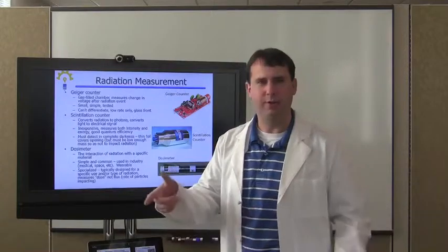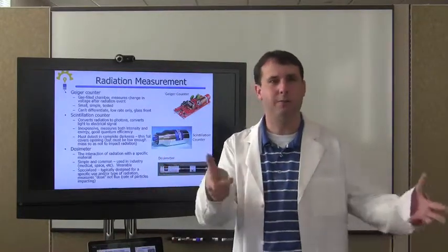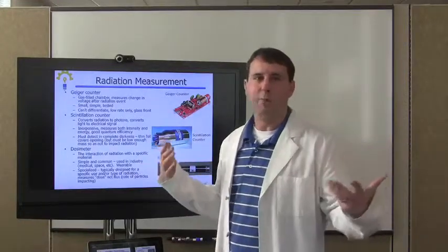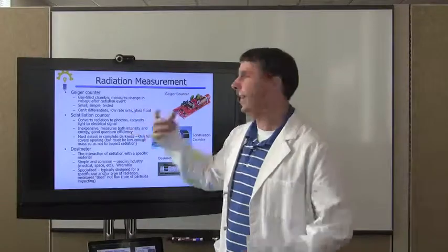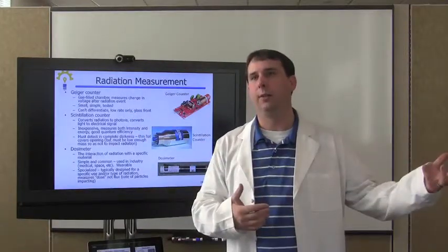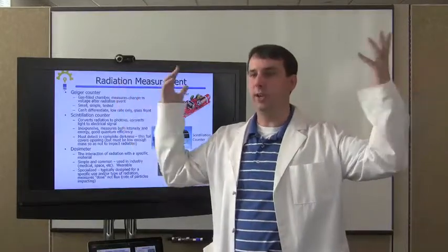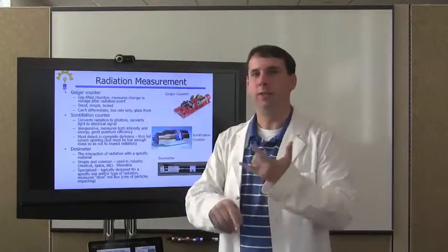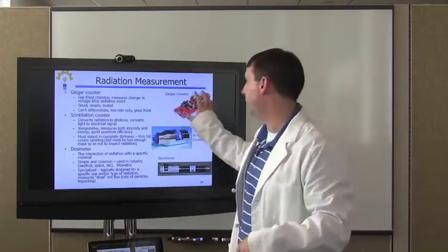You've all heard that noise of radiation. That's the output you hear from a Geiger counter. And they can't differentiate between the energy of the different particles, because it just measures the voltage across. It says, okay, radiation is in there. I don't know whether it's alpha, gamma, or whatever, but it just measures radiation. So that's how Geiger counters work.